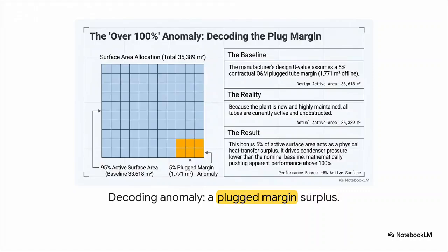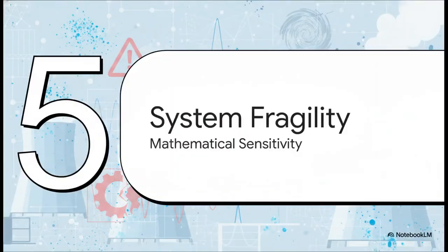Now, I know some of you are looking at that 101.42% result and thinking, wait a minute, how on earth can something be over 100% clean? That's physically impossible. It's a great question, and this slide decodes that exact anomaly. When the manufacturer designed the baseline, they baked in a 5% contractual O&M plugged tube margin. Essentially, they assumed 5% of the surface area would eventually be taken offline for maintenance. However, because this specific plant is so highly maintained, all 100% of the tubes are currently active and unobstructed. See that orange block of tubes in the diagram? That is a physical heat transfer surplus. It drives the pressure slightly lower than the baseline expects, which mathematically pushes our apparent performance just over that 100% mark.